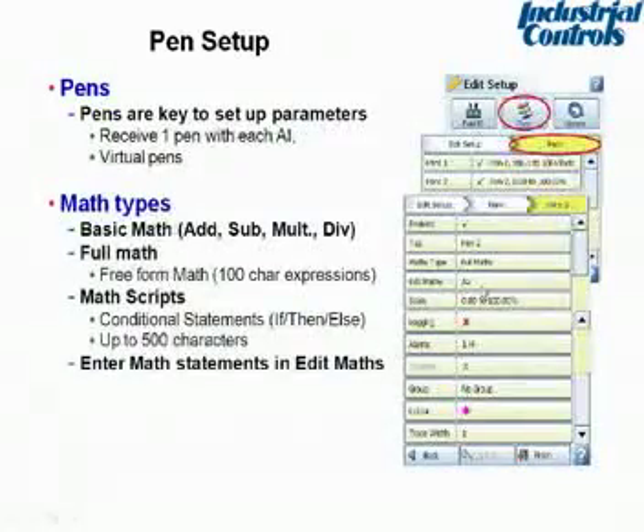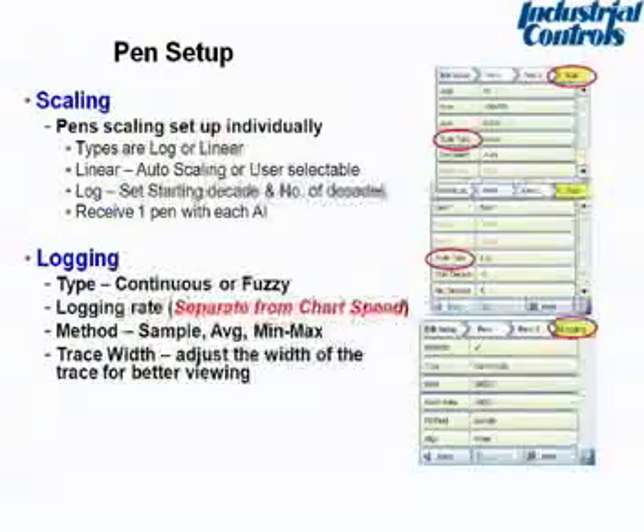Also in this part, you have the opportunity to put math in. So for example, we've got pen 2 here, and if you just put A2, that means you're basically trending or putting on the chart the value of analog input 2. But you could very easily use math in there and say, let pen 2 equal the total of pen 1 plus pen 3. So you can do some nice, interesting math, and we'll talk about some examples.